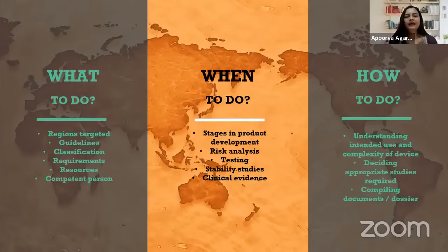Now, this will also be driven by the risk analysis of that particular device. If I quickly explain what a risk analysis is, this is a document. It's a living document. Living document means it keeps updating at every product development stage. So it has the hazards, the hazardous circumstances, and the harm. And it has probability of occurrence and the severity of occurrence of something. Based on all these factors, there is a mathematical number which is calculated, and manufacturers try to decrease the risk of that particular hazardous situation or harm to ensure that they comply with regulatory requirements, guidelines, and such. So, this risk analysis document would dictate a lot of the when to do's.